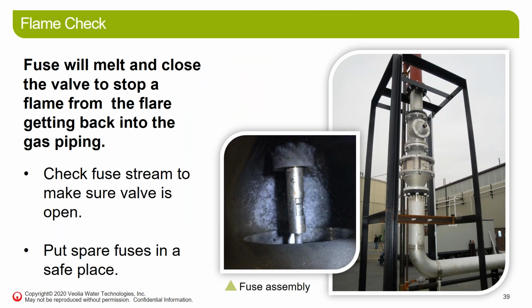Again, another form of backflash prevention, a thermal check. If you see here on the picture on the right, it's a vertical installation of a thermal shutoff and a flame arrestor. So if you ever got a backflash, that fuse would melt inside there and cause the valve to close. Then you would have that flame arrestor as well. So when you're down, it's important to check this fuse, make sure it's open, have some spare fuses, possibly replace these on some frequency. Again, always important to check this when you're down.